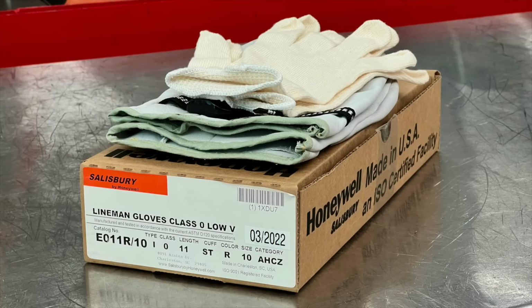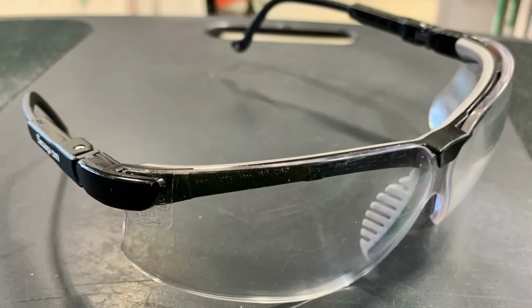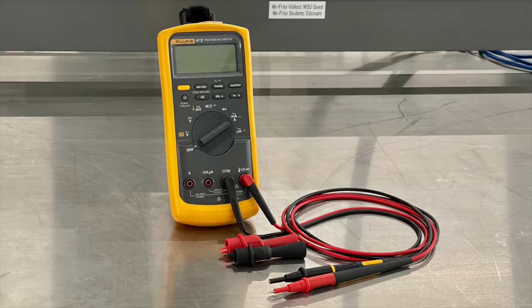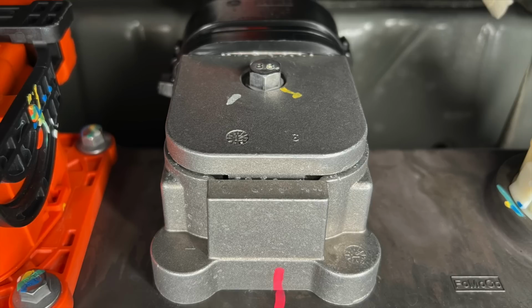Wait 5 minutes for the inverters' capacitors to go through a passive discharge, then put on high voltage personal protective gloves, the leather outer protectors, and all your other personal protective equipment. Grab a category 3 multimeter that's been verified as working properly, and get down there and unplug the inverter connection at the front of the battery.